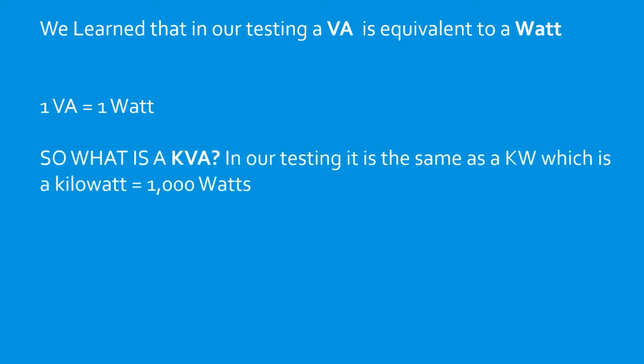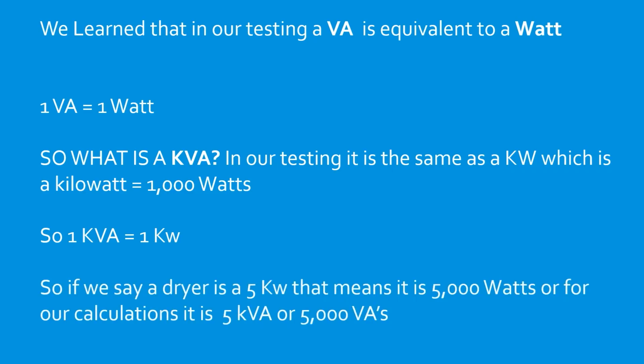So what is a kVA? And in all of our testing, it's going to be the same as a kW, which is a kilowatt, which equals 1,000 watts. So 1 kVA is equivalent to 1 kW. And you're going to hear them used interchangeably in your testing and also in these lessons. So if we say that a dryer is 5 kW, that means it's a 5,000 watt dryer. Or for our calculations, you may hear it called 5 kVA, which is equivalent to 5,000 VAs.